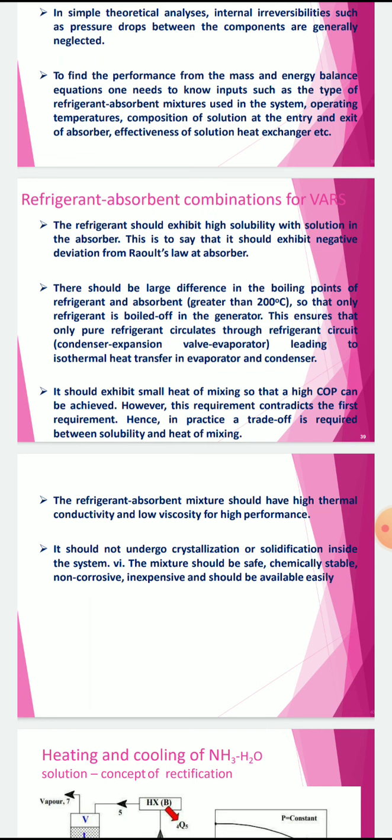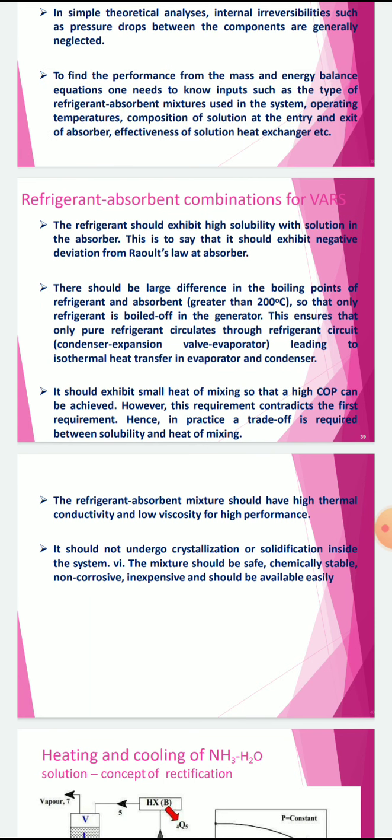It should exhibit small heat of mixing so that a high COP can be achieved. However, this requirement contradicts the first requirement. Hence, in practice, a trade-off is required between solubility and heat of mixing.